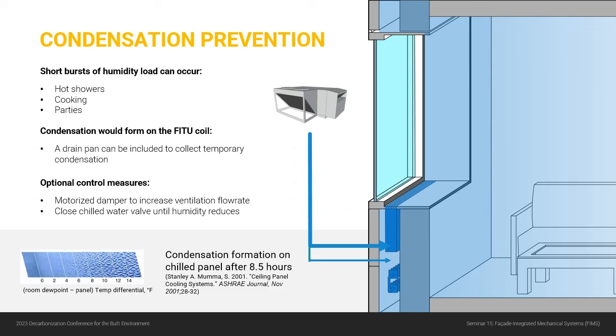Now, some of you may be thinking, humidity loads are relatively low in an apartment, except you do get these short bursts of humidity sometimes, right? You have hot showers, people cooking, large gatherings, you can have higher humidity loads. So what happens then? The first thing to point out is that if you do get condensate forming, it's going to form on that coil in the FITU. So what's going to happen is it's going to drip into the base of the FITU. So it's not a situation where you're going to have droplets dripping onto your head or onto your computer from the ceiling. So it'll drip into the FITU, and then when that moisture load goes away, it'll quickly dry out because we're supplying that dry ventilation air directly into the FITU.